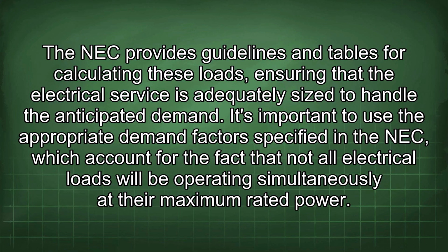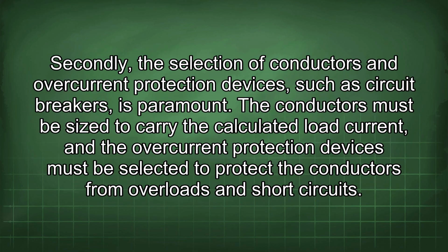It's important to use the appropriate demand factors specified in the NEC, which account for the fact that not all electrical loads will be operating simultaneously at their maximum rated power. Secondly, the selection of conductors and overcurrent protection devices, such as circuit breakers, is paramount. The conductors must be sized to carry the calculated load current, and the overcurrent protection devices must be selected to protect the conductors from overloads and short circuits.